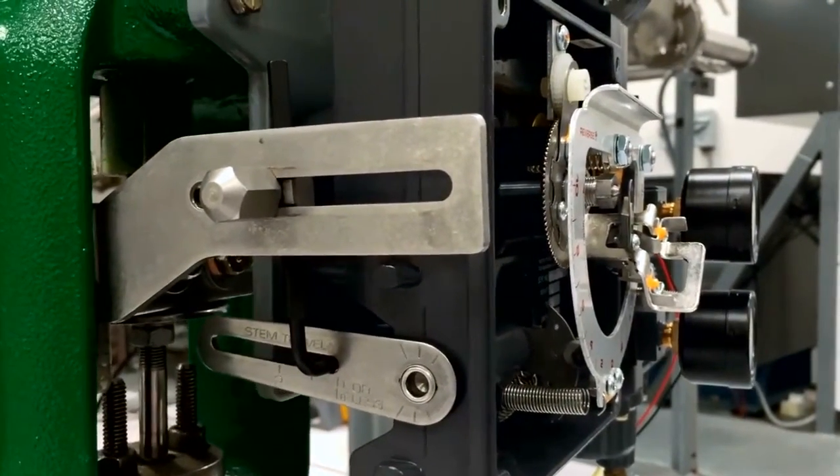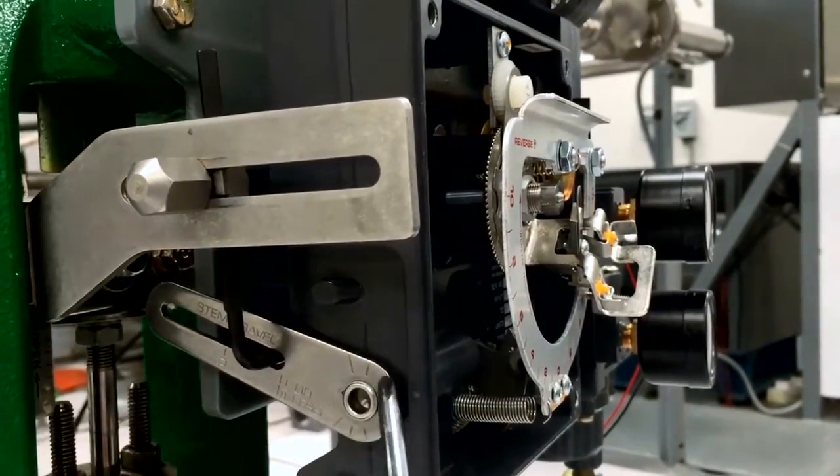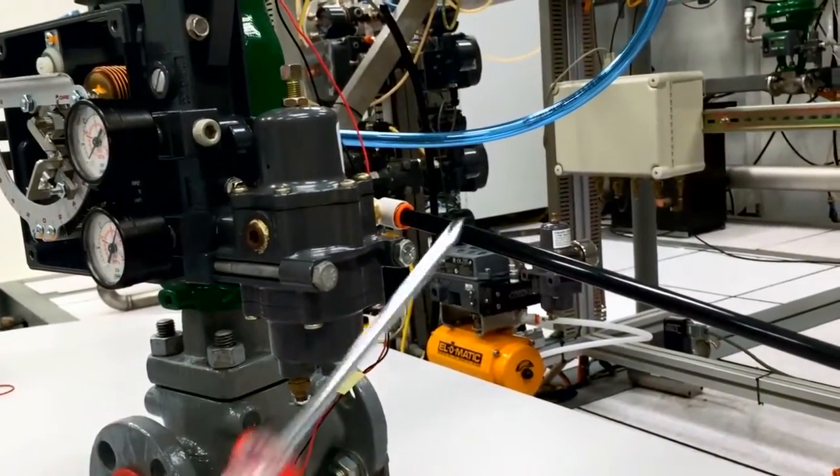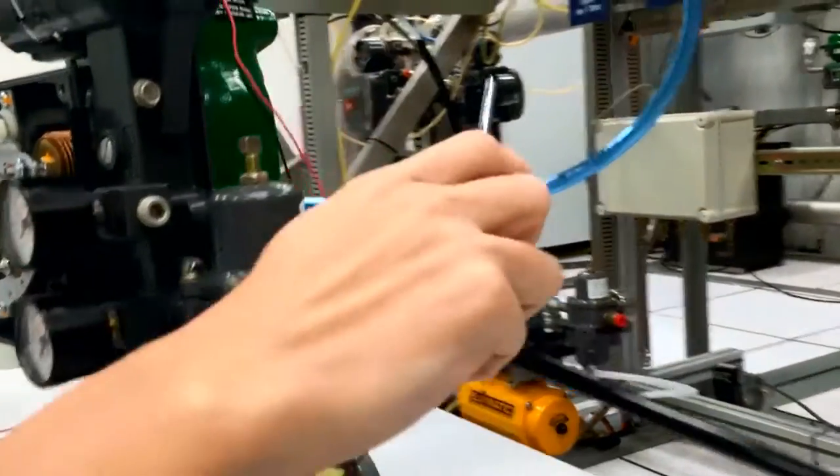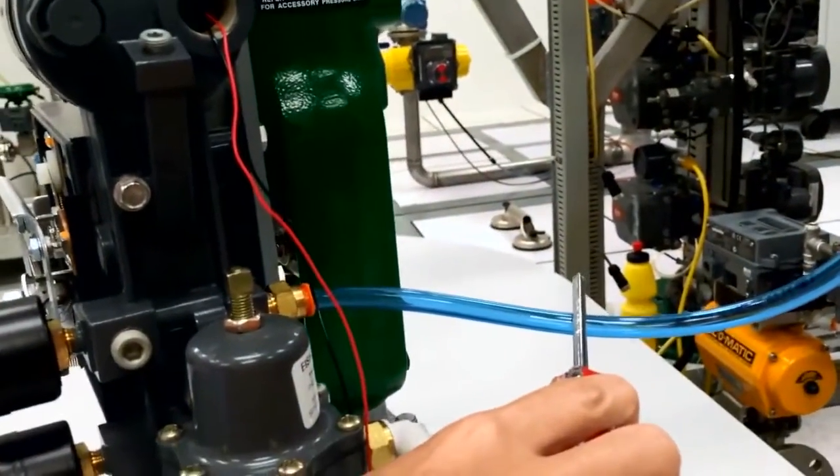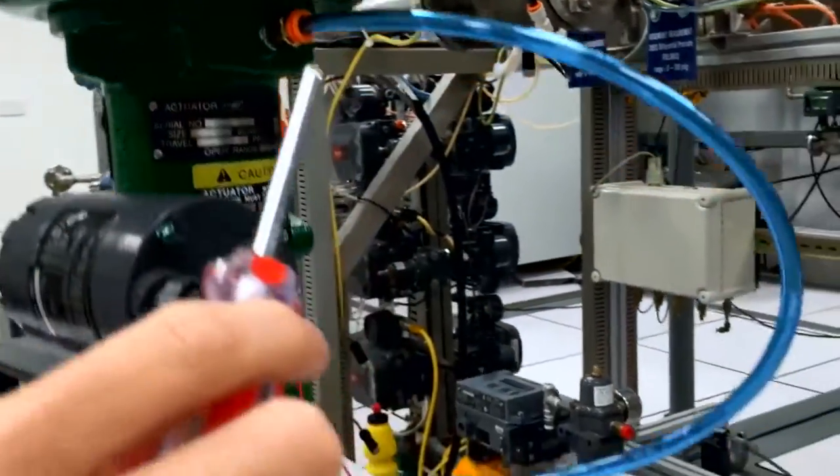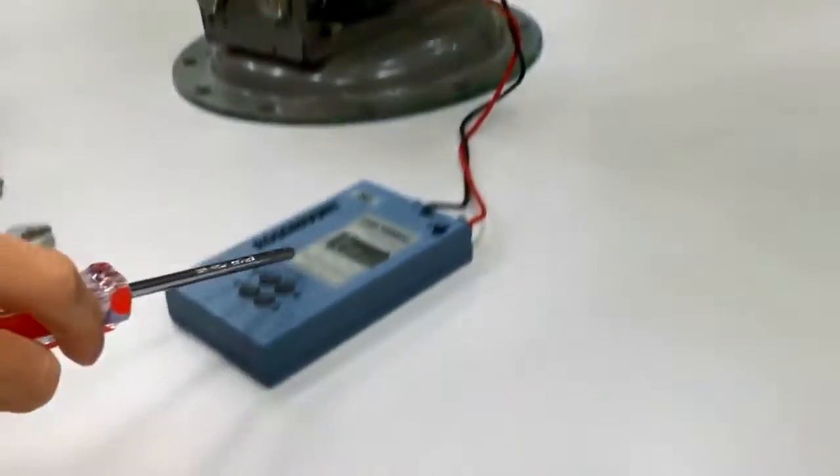The next check is for the pneumatic and electrical connections. The air supply is connected to the regulator which supplies air to the 3582i. The output of the 3582i is connected to the actuator. The electrical connections are connected to the 3582i module to the power source generator.